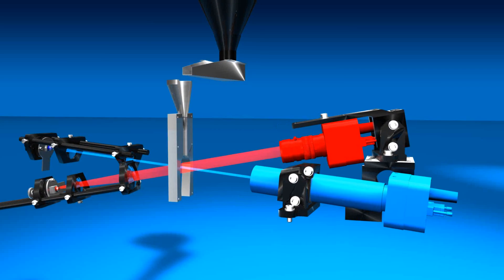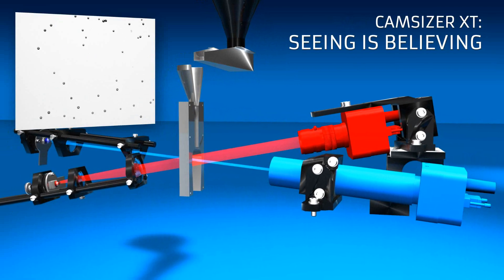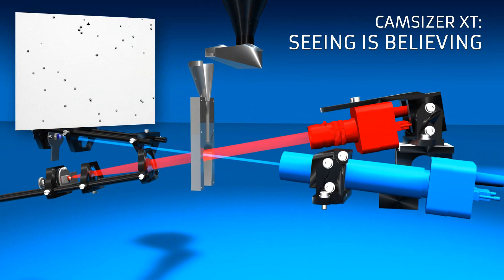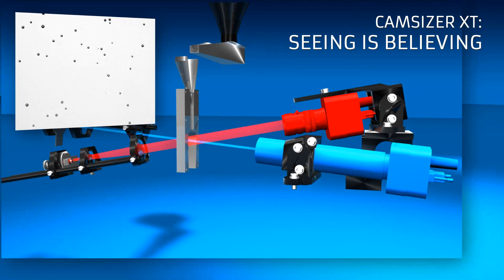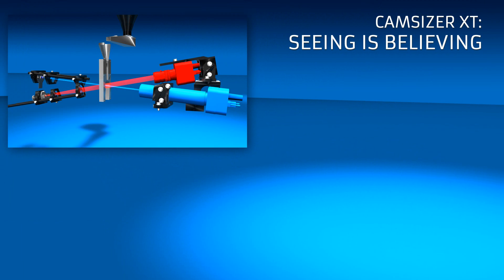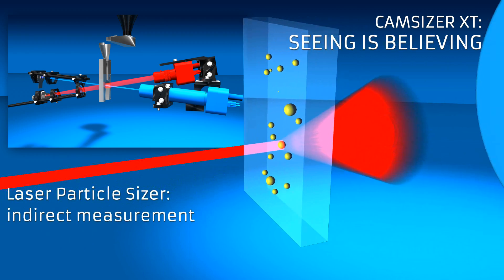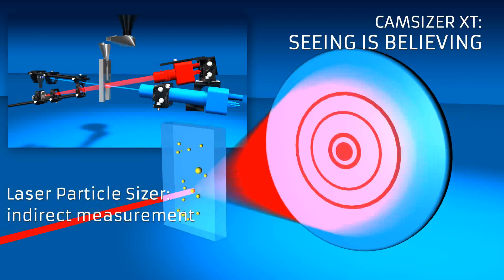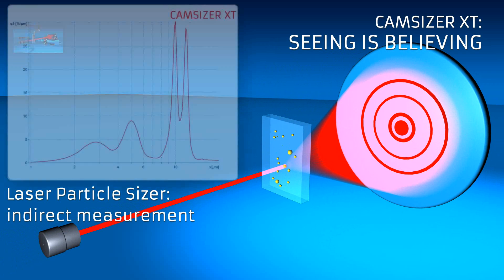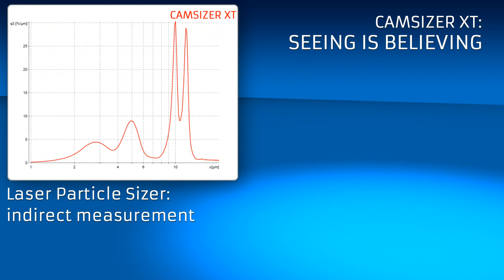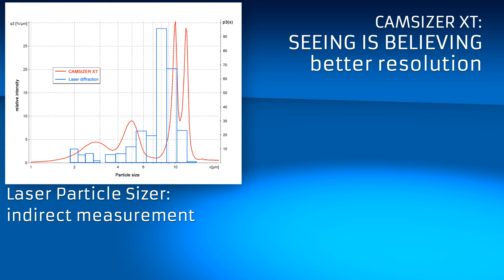The measurement principle of the CamSizer XT is simple and direct — seeing is believing. The information obtained from pictures allows for a much better understanding of the sample properties than the size information calculated by the indirect measurement principle used by laser diffraction analyzers. Whereas the CamSizer XT can resolve mixtures of 2.5, 5, 10, and 12 micrometer particles accurately, this is a serious problem even for state-of-the-art laser scattering instruments.